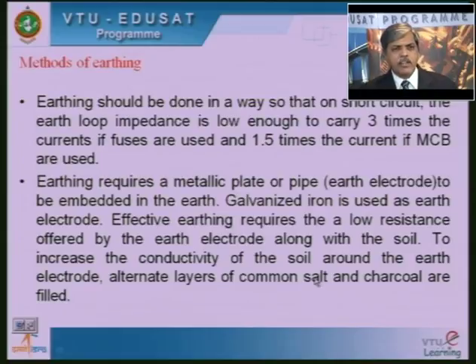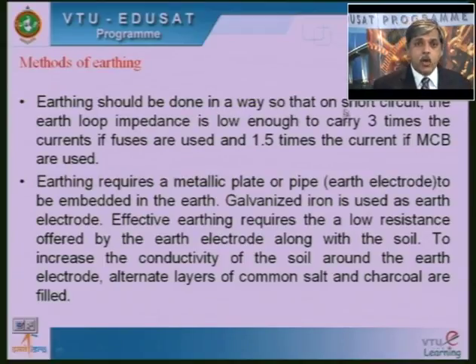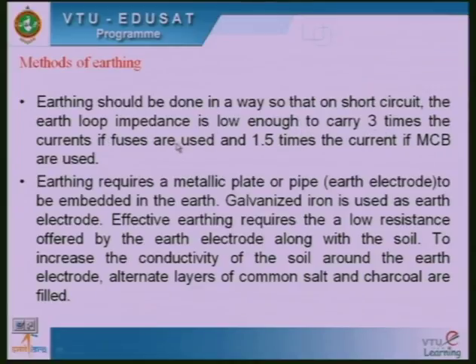Different methods of earthing are there, particularly we use 2 types. Earthing should be done in a way so that on short circuit the earth loop impedance is low enough to carry 3 times the current if fuses are used and 1.5 times the current if MCBs are used. Earthing requires a metallic plate or a pipe, called an earth electrode, to be embedded in the earth. Galvanized iron is used as the earth electrode.